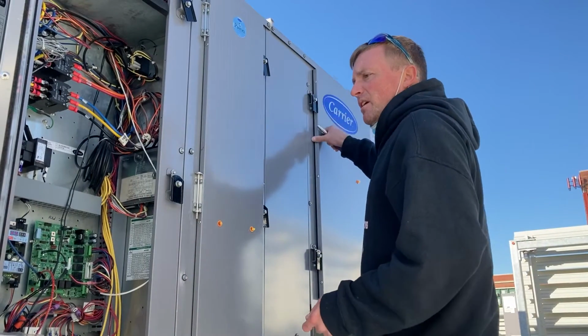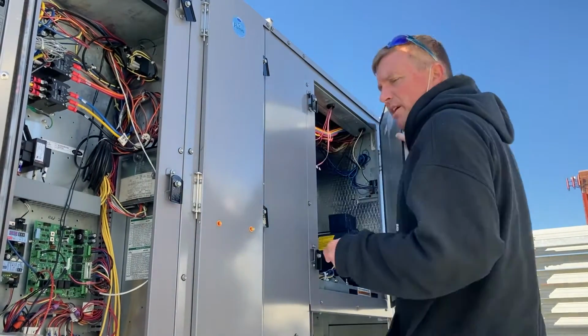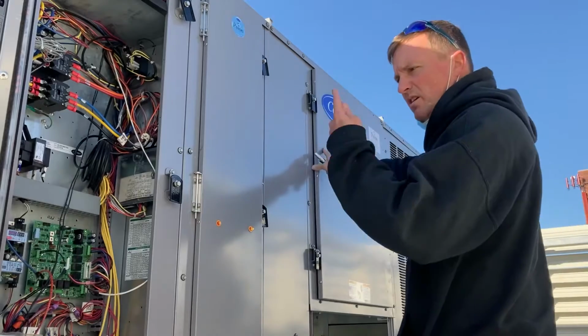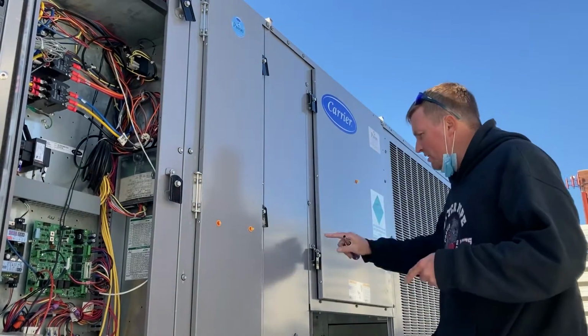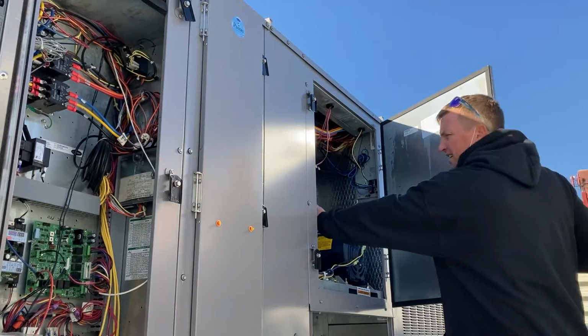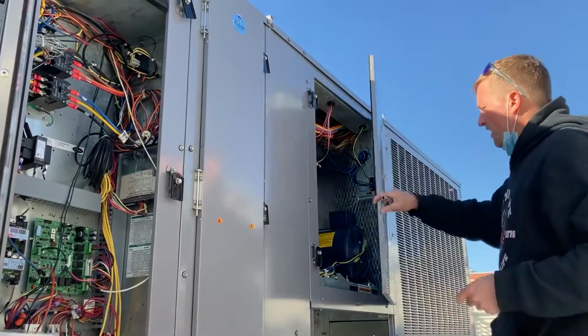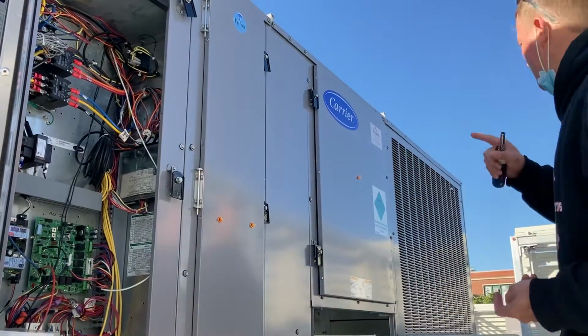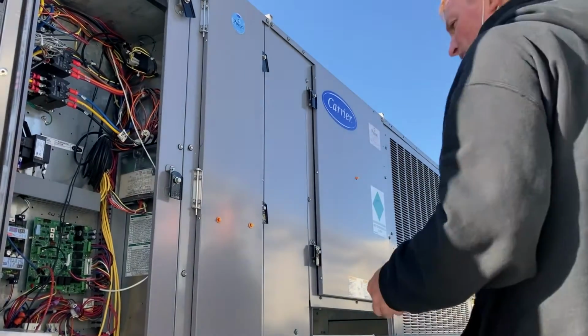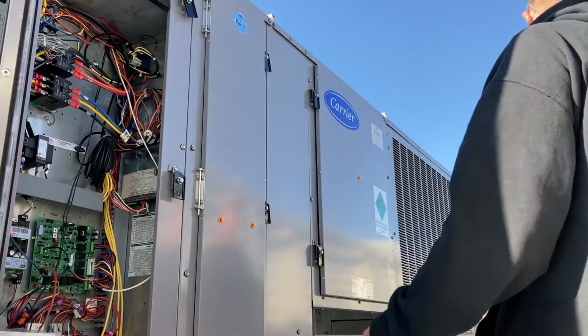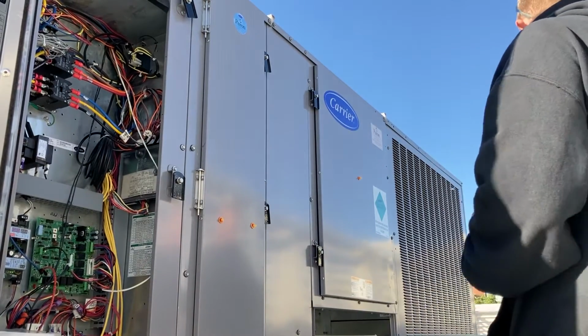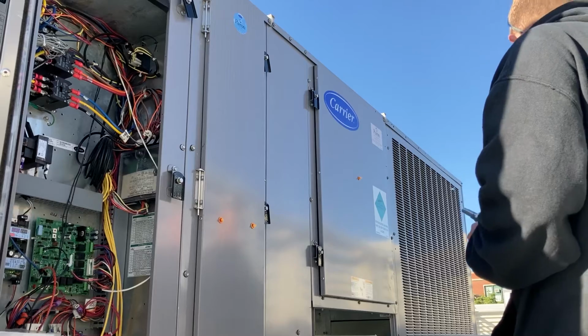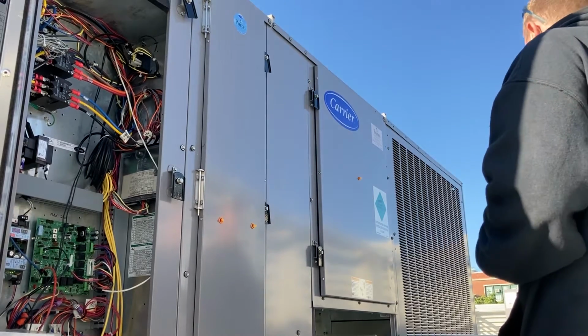So first thing is the VFD. All the equipment here on site, both this 50LC and the one next door, meaning electrical heat, have a VFD. The VFD basically ramps the unit's fan up and down based on static, because we have VAVs here. So the VAVs open up, speeds up, comes down.